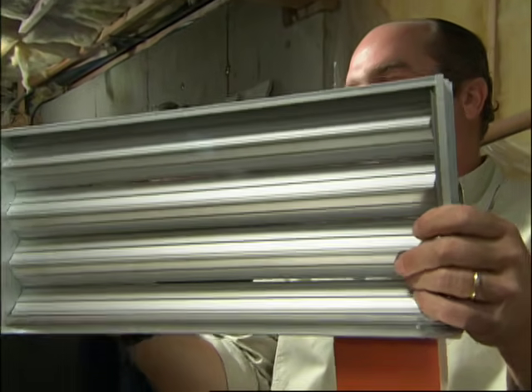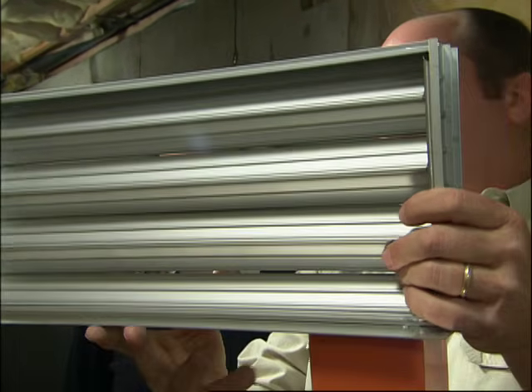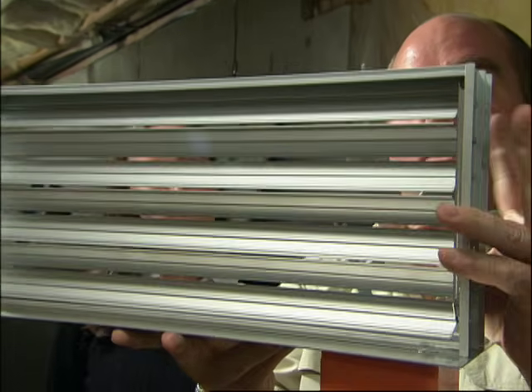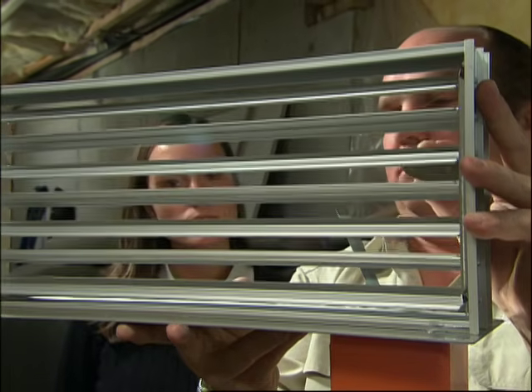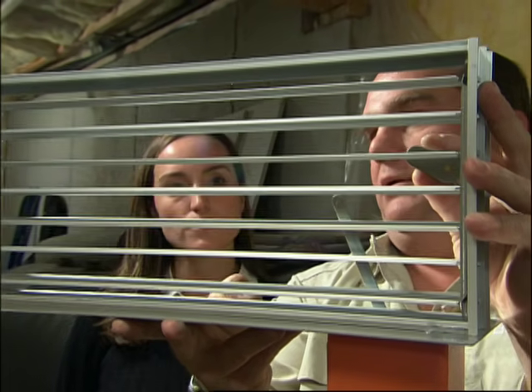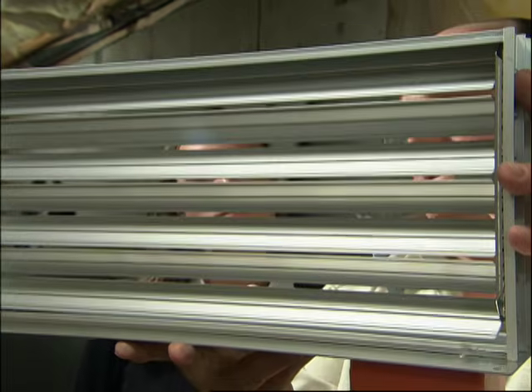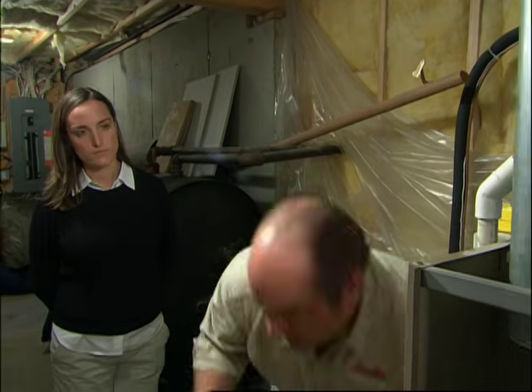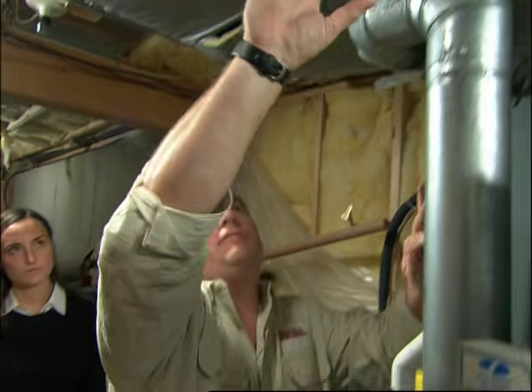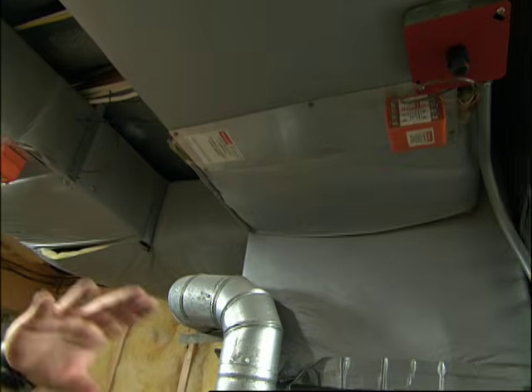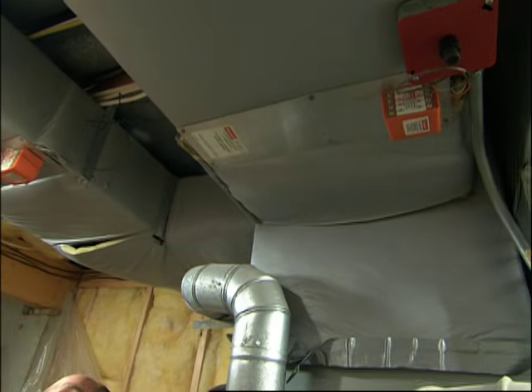Now when the thermostat is satisfied, this is what it looks like. Okay. With a call for heat, now the motor opens these blades like that, and it's open. Thermostat satisfied, it closes like this. Now imagine what happened when this first installer did the ductwork system here. Let's say that he designed it for 50% of the airflow to go to the second floor and 50% to go to the first floor.